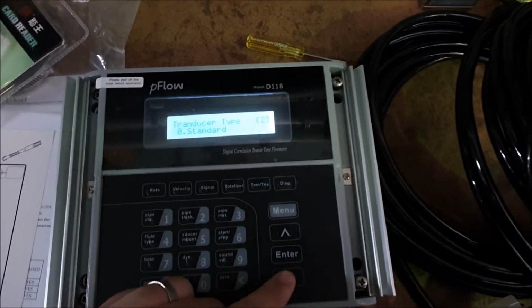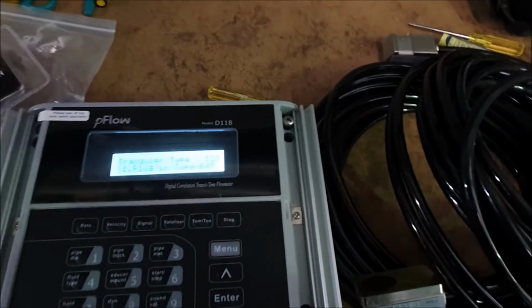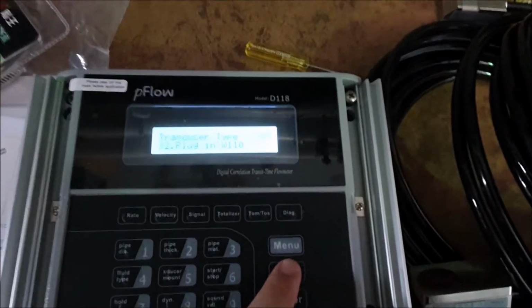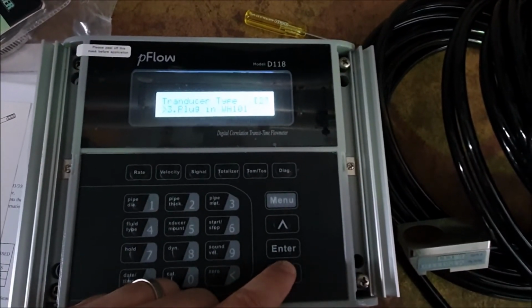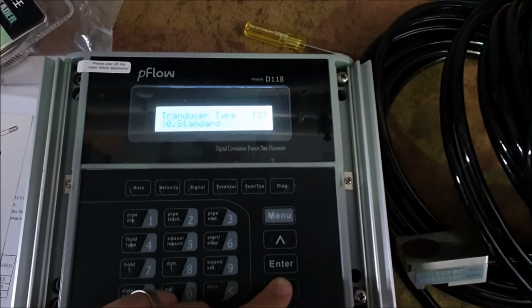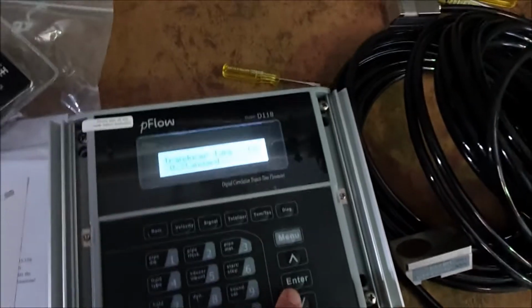Transducer type is going to be standard every time. For this one, there's only one set of transducers that is relevant. There's also a plug-in and insertion type, but standard for an ultrasonic clamp-on is the correct one to use.